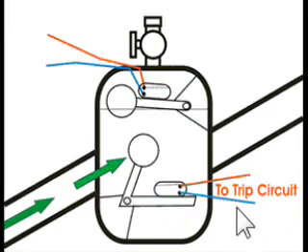This switch energizes the trip circuit of the circuit breakers associated with the transformer and immediately isolates the faulty transformer from rest of the system by inter-tripping the circuit breakers associated with both LV and HV sides of the transformer. This is how Buchholz relay functions. Thank you.